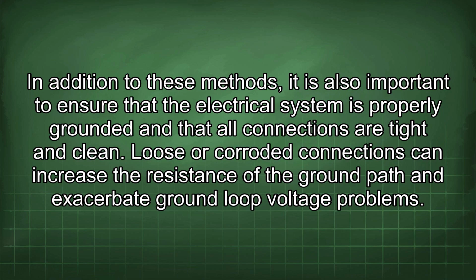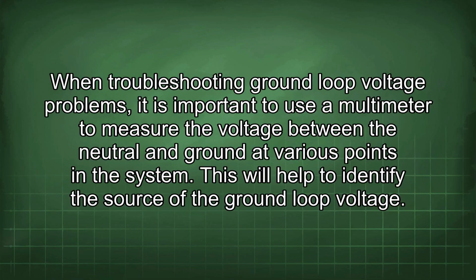Loose or corroded connections can increase the resistance of the ground path and exacerbate ground loop voltage problems. When troubleshooting ground loop voltage problems, it is important to use the multimeter to measure the voltage between the neutral and ground at various points in the system. This will help to identify the source of the ground loop voltage.